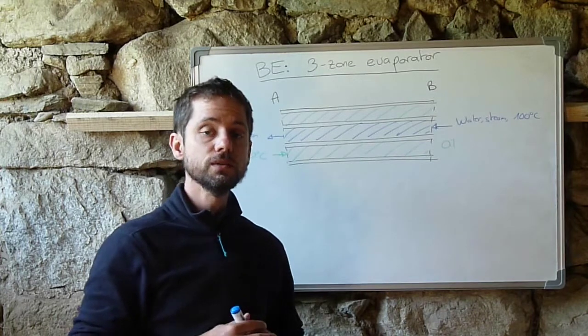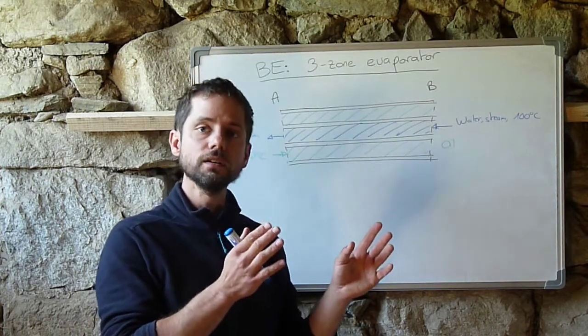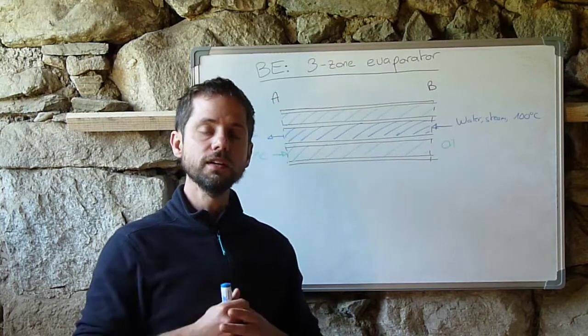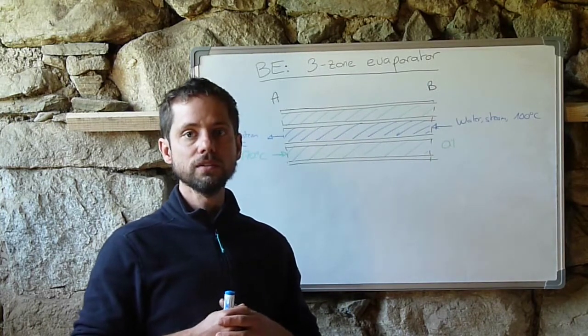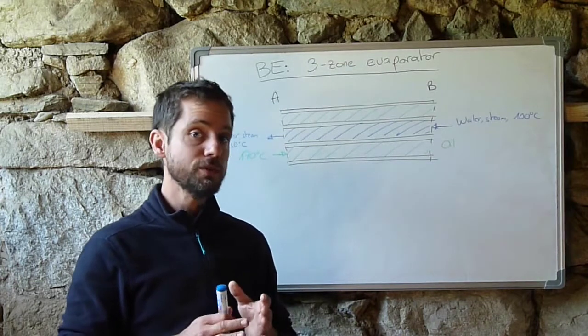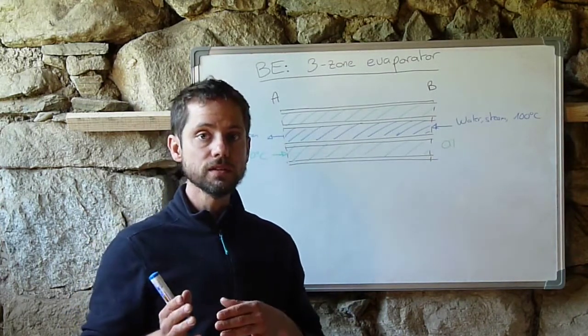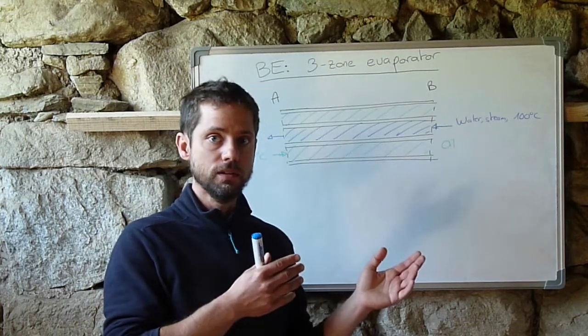So here, in order to size the heat exchanger, we need to size separately each subsection of the heat exchanger because the heat transfer coefficient will be very different if the water is liquid or evaporating or vapor.